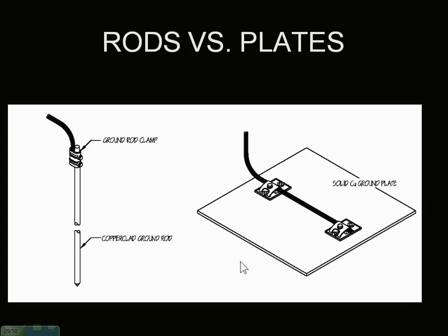When we do grounding for a building, you're going to have 3 grounding systems in every building: one for low voltage - coaxial cables, phones and so forth; one for lightning; and one for the electrical system. These 3 systems are interconnected, or they could be one combined system. That's why when you mentioned 5 ohms, that's typical in the telecommunication industry for towers - they require you to have 5 ohms or less.